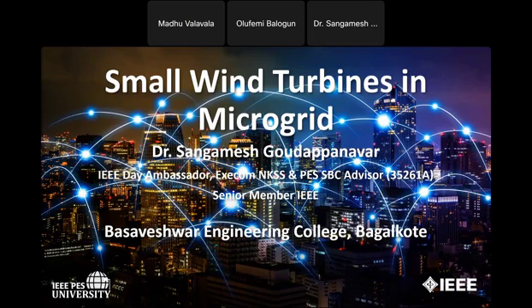Small wind turbine generators in the range of 1 kilowatt to 5 kilowatt are more suitable for penetration on the low tension side of distribution system microgrids, particularly for low wind regimes. As per the Indian Grid Code and Karnataka State Electricity Regulatory Commission, voltage variation is allowed up to plus or minus 9% and plus or minus 6% for HT and LT respectively.